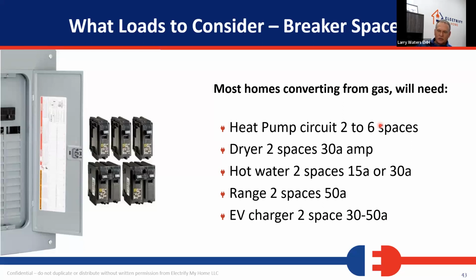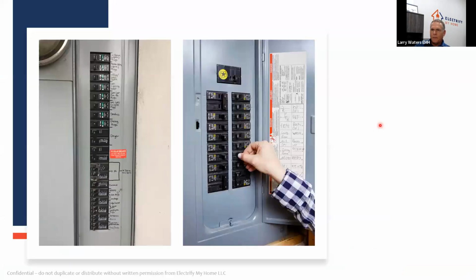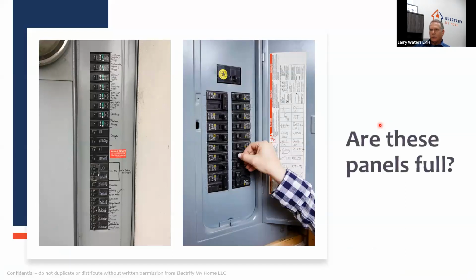And then range spaces, we're going to need a 50 amp for that range. And if they've got a cooktop and an oven separate, we have to think about that. And then the EV charger, 2 spaces, or maybe we share a circuit, something like that. So a lot of additional capacity needs to be added in. If we do this smart, it has less impact. So we see a couple of breaker panels here. And the question we ask is, are these panels full? And the answer is maybe or maybe not.